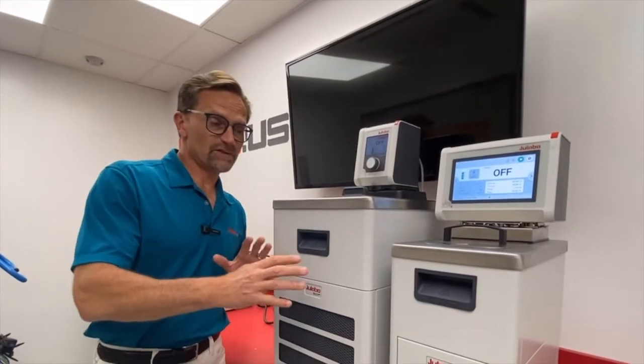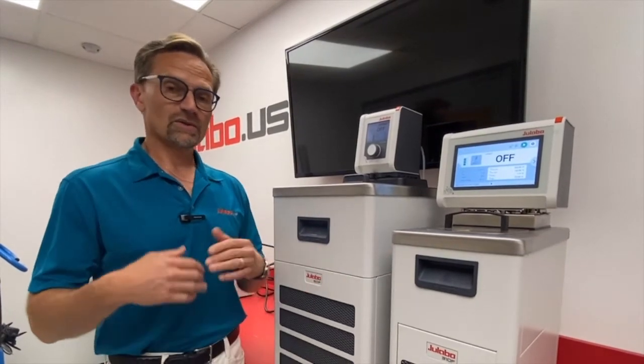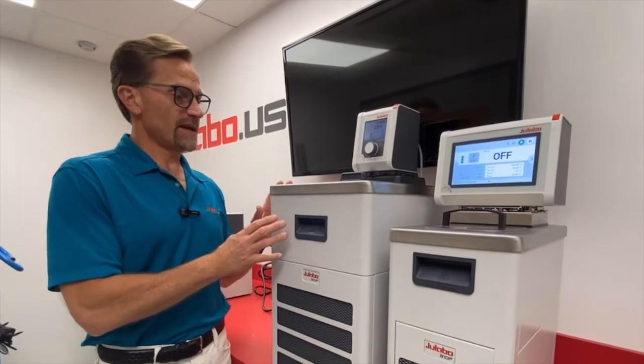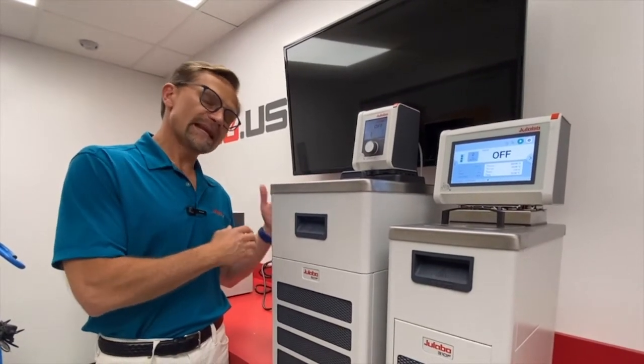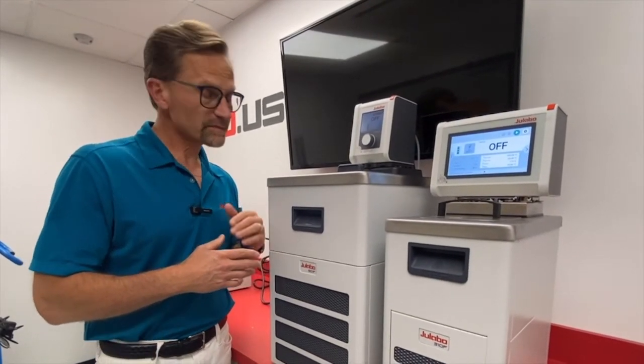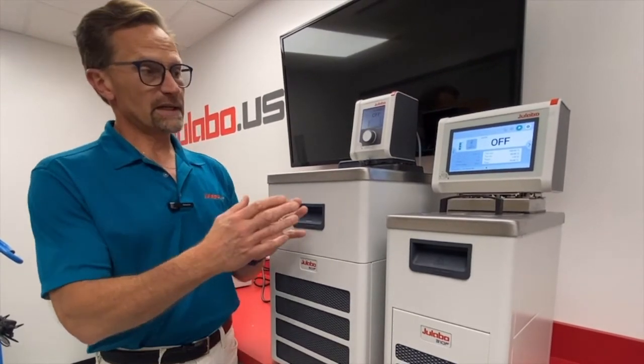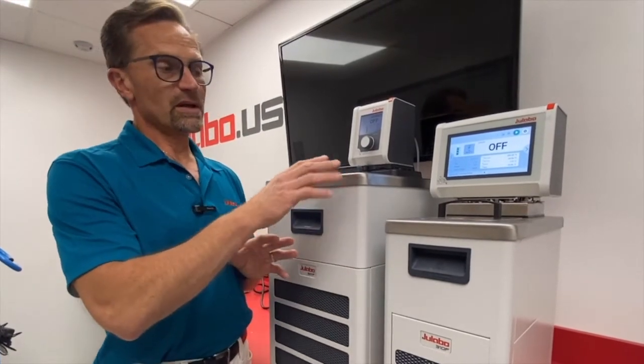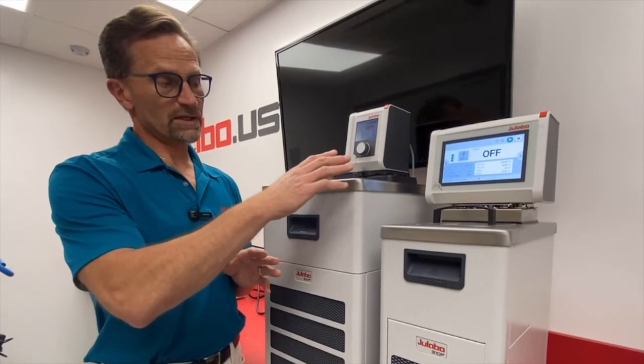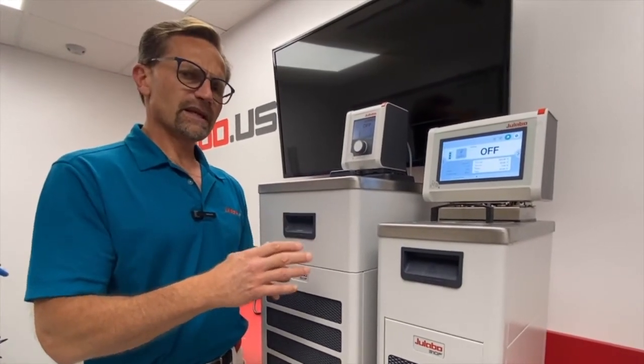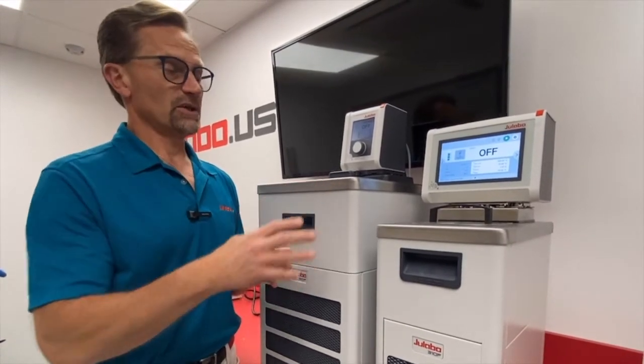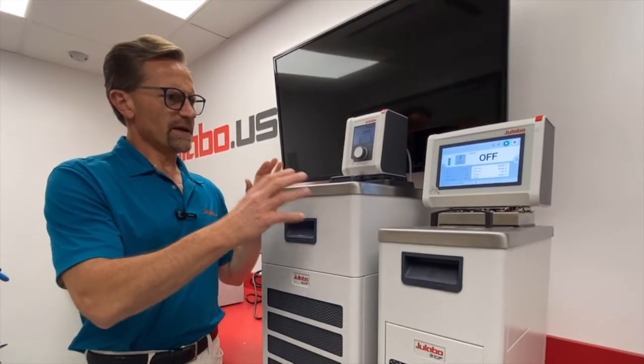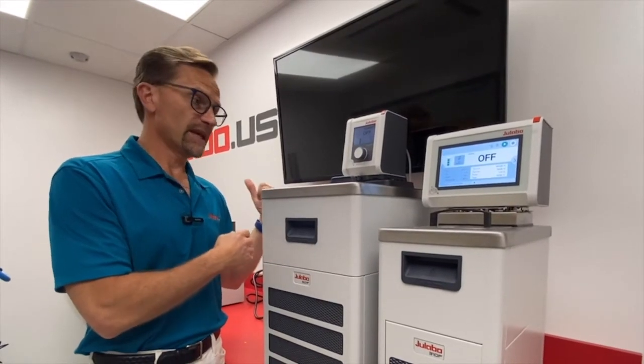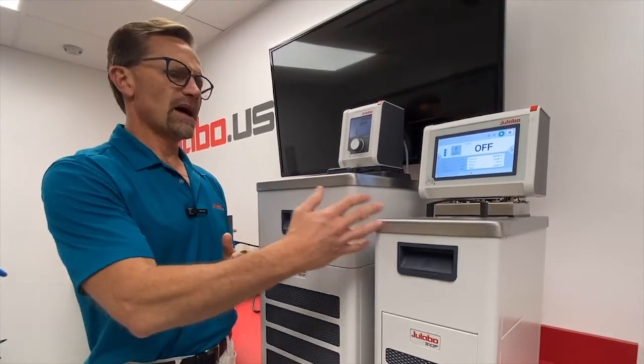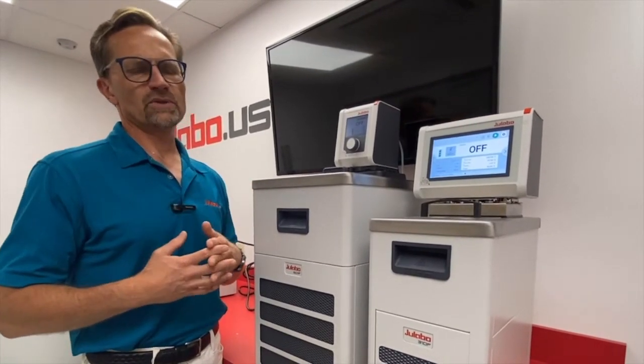All right, so we just reviewed the differences and features of the DYNEO DD products and the MAGIOs. So what would lead you to choose one or the other? Remember, for the DYNEO, you have a smaller pump capability, and from a heating perspective, you only have 1 or 2 kilowatts heating power with a max temperature of 200 degrees C. Whereas on the MAGIOs, you have a stronger pressure suction pump, a lot more communication options in addition to the user touchscreen, and the heating circulators can go to 300 degrees C, and you have up to a 3 kilowatt heater in the MAGIO model line. So both units incorporate external PT100, which is great for controlling from your application. But if you have a stringent calibration protocol, then the MAGIO has the optional 10-point calibration, which gives you that tighter calibration curve, whereas the DYNEO only has up to a 3-point calibration.